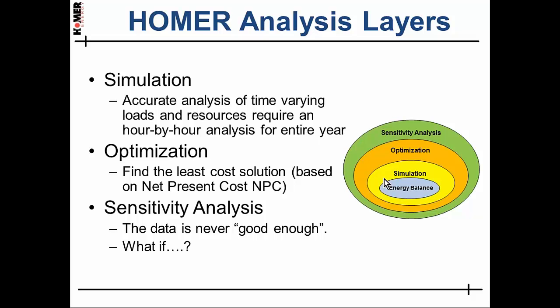If you haven't tried it, the new optimizer makes optimization faster, simpler, easier, and more robust, which we find leads to less user error. Now, just as optimization is a set of simulations, sensitivity analysis is a set of optimizations. When we perform a sensitivity analysis in HOMER Pro, we're exploring how the optimal design, that is, the things that a designer can control, change when we change things a designer cannot control.